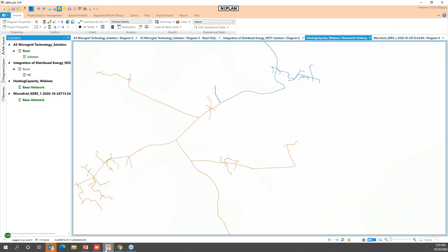The optimal power flow solution was for an economical dispatch, where what I did was define the highest cost coming from the external network, a medium cost in the synchronous machine, and a low cost using the inverter. NEPLAN is suggesting these new set points for our synchronous machine. This is a suggestion for an economical dispatch, and it allows us to implement the tertiary control of the microgrid.